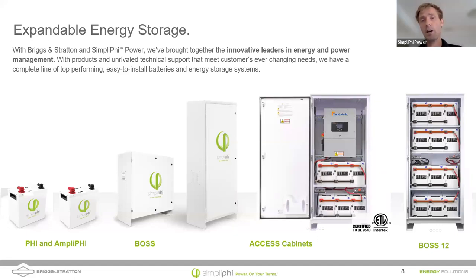And as I said, our high voltage solutions typically are in the 600 to 1200 volt range. The reason for this is once you start trying to pull large amounts of power from a battery bank, those currents can be significantly high. So at 100 amps at 50 volts, that's 5,000 watts. If you want to do 50,000 watts, you're looking at 1,000 amps. What if you want to do 1 million watts, a megawatt? Then you're looking at very high currents. Because the product of current times voltage gives you power, if you increase the voltage, you can decrease the current so that you don't need 4-inch large diameter copper wiring.